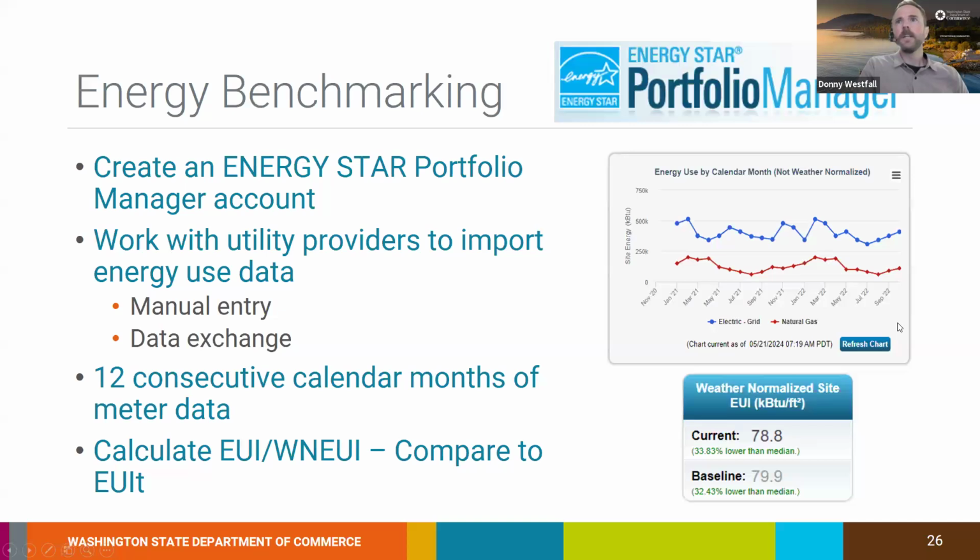So most of you are familiar with the benchmarking requirements for Clean Building Standard. Campuses complying through the Decarb of their district energy systems must still comply with the performance metric requirement of the Clean Building Standard. Part of that process is calculating an EUI for the building, or in this case, the aggregated EUI for a campus using 12 consecutive months of energy use data. And then how do we do it? We utilize Portfolio Manager to track building energy use and report EUI for compliance.